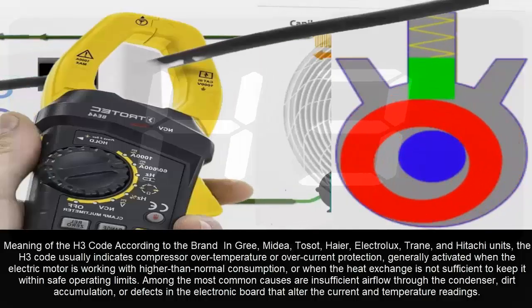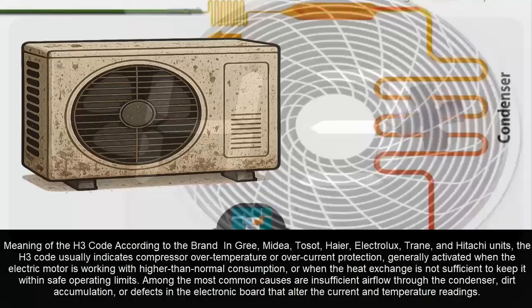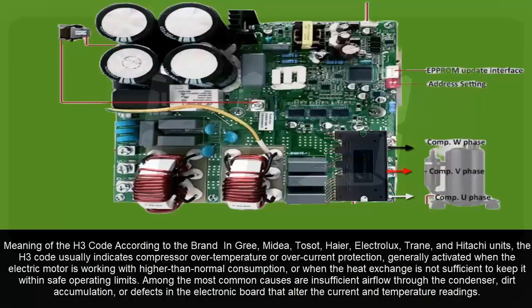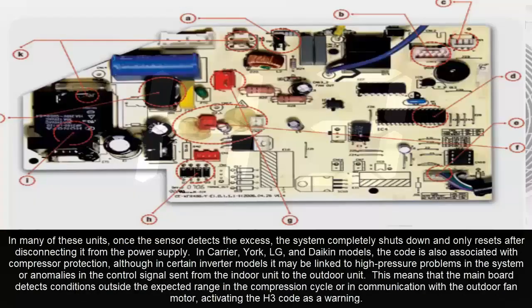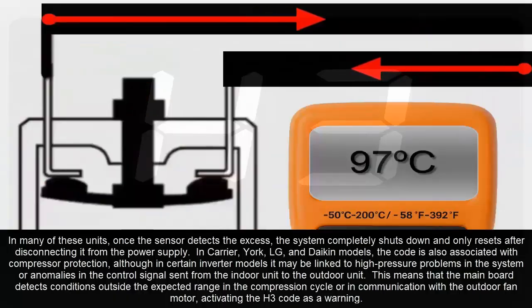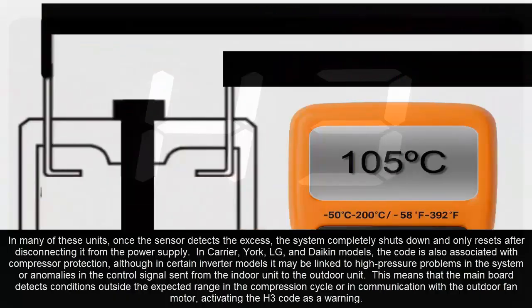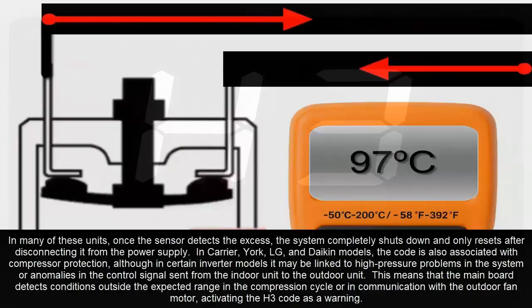Among the most common causes are insufficient airflow through the condenser, dirt accumulation, or defects in the electronic board that alter the current and temperature readings. In many of these units, once the sensor detects the excess, the system completely shuts down and only resets after disconnecting it from the power supply.